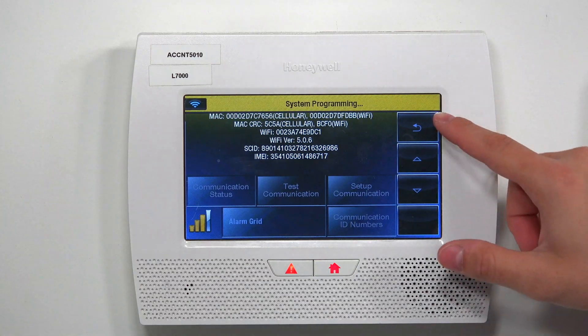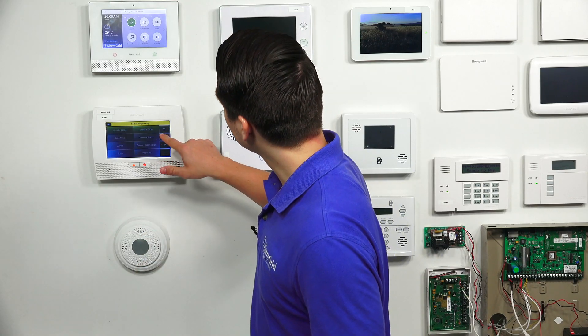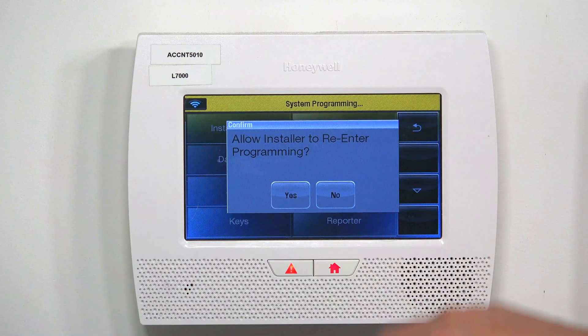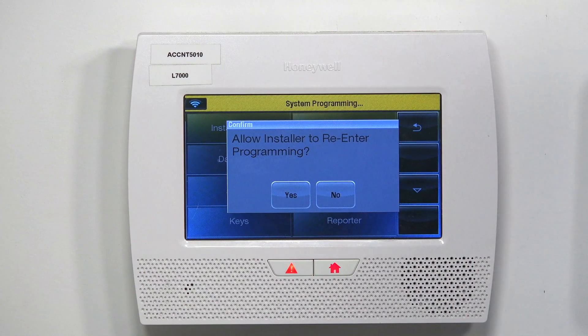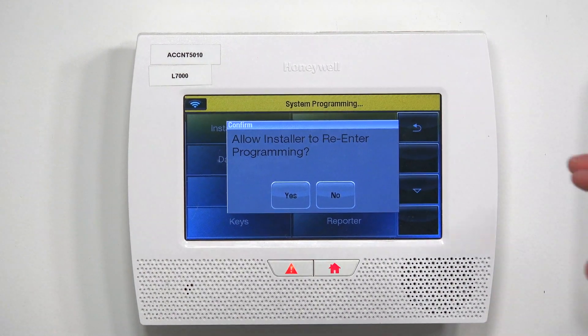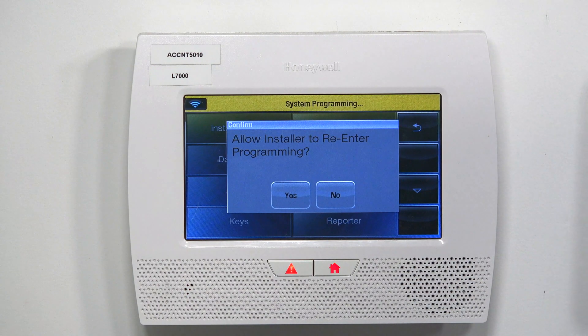Once you have found that information and relayed it back to your alarm monitoring company, hit the back arrow until you go all the way back to the main screen. You're going to get a window every single time that says 'Allow installer to re-enter programming' — you're always going to choose yes. If you ever press no, you are going to be locked out of programming.